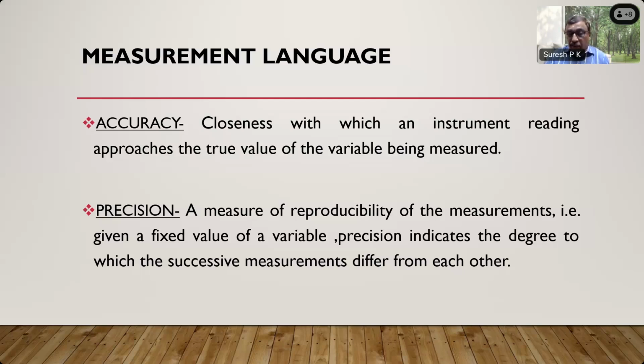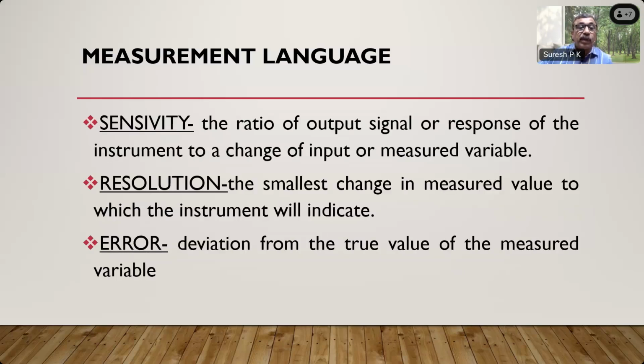The precision. You will always say precision is a measure of reproducibility of the measurement, that is, given a fixed value of a variable. Precision indicates the degree to which successive measurements differ from each other. That is, if you measure a particular value or a particular temperature 2 times using an instrument and it gives 2 totally different readings, then what is the reliability of that measurement? So the precision, or the reproducibility of the measurement using the instrument, is very important. Precision is very important for any instrument.